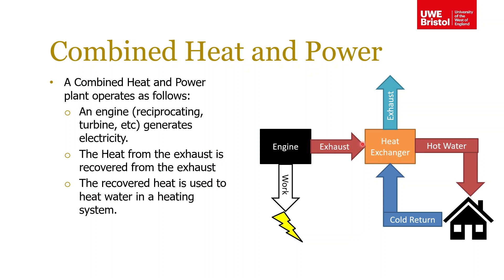Those exhaust gases go into a heat exchanger, where they transfer heat to the water in a secondary circuit. I've shown a home in this instance, but it could be an industrial process or something else. The heat is extracted here — we have a cold return that gets heated — and we vent cooler exhaust gases. Rather than just wasting the heat from the exhaust, we are using it to do something useful.